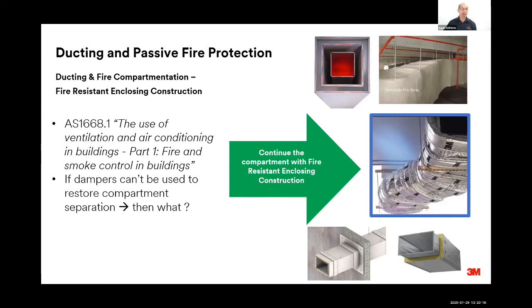So if we can't use fire dampers to restore the fire resistance rating, the alternative is to effectively continue the compartment all the way through the building. We can do that by enclosing the duct with a fire-resistant enclosing construction.